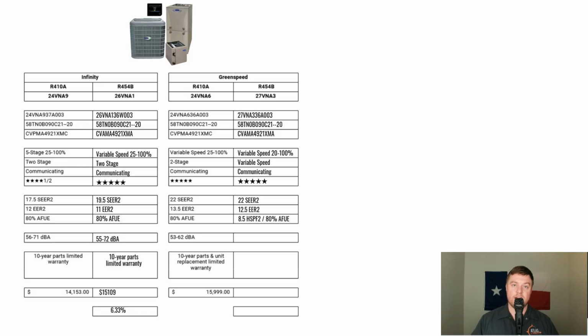Now where things get interesting is the heating efficiency. So both furnaces that I have spec'd in are identical. In heating, it's operating at 80% AFUE. Now, by installing a heat pump, the majority of the winter as your system is heating, it's going to be using the heat pump. So it's not going to be using any gas, but electricity, and is far more efficient than an 80% furnace. So in the wintertime, the 27 VNA3 is going to be quite a bit more efficient than an 80% furnace.